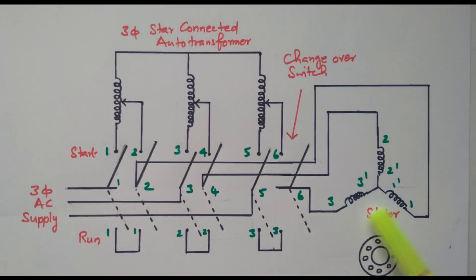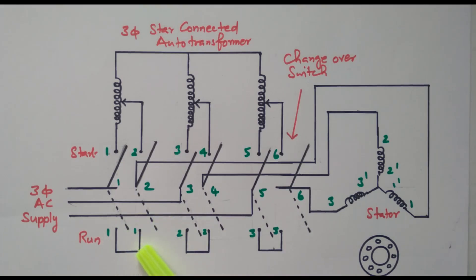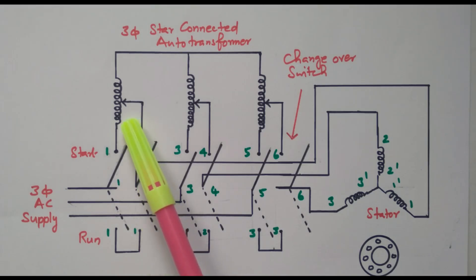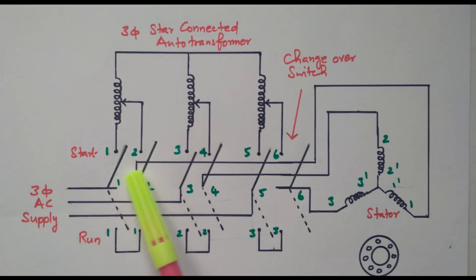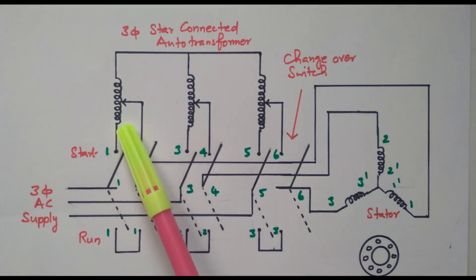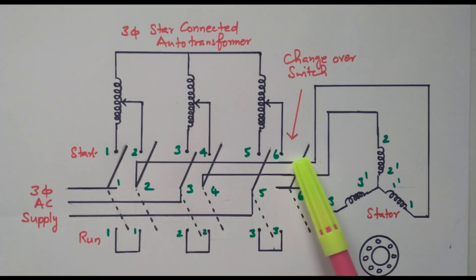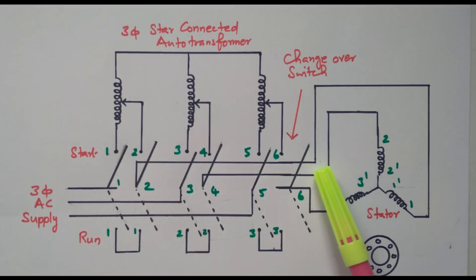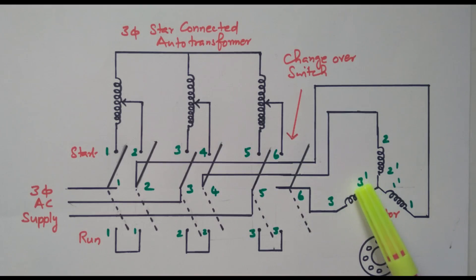Once the motor starts at the rated speed, the changeover switch is placed in the running position. During the running position, the entire voltage is applied, and the motor rotates at the rated speed by taking the rated current and rated voltage. The auto-transformer initially reduces the voltage applied to the stator to reduce the high starting current. By slowly changing the position, the voltage applied to the stator is gradually increased until the motor takes the full rated current and rated voltage and rotates at the rated speed.